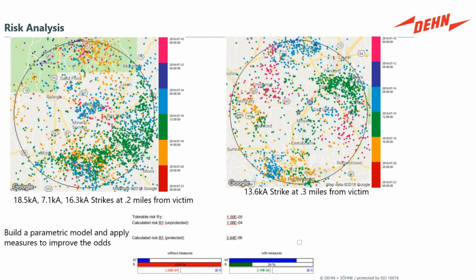I just want to draw attention that it does pay attention to isolated lightning protection systems. So lightning risk starts with the analysis of your application. Are you a hospital full of babies and liquid oxygen? Are you a charging station with lots of humans nearby? And you calculate your risk if you don't apply protection, and you apply protection to reduce that risk below a tolerable threshold. So there's industry standard tolerable risk reference levels. For instance, human safety is 1 in 100,000. So if your risk is too high, you reduce it below 1 in 100,000. And that's the whole point of this chart at the bottom. It's basically giving you the blue threshold and the red out of control risk, and then the green under control. Now you've reduced the risk below the thresholds.